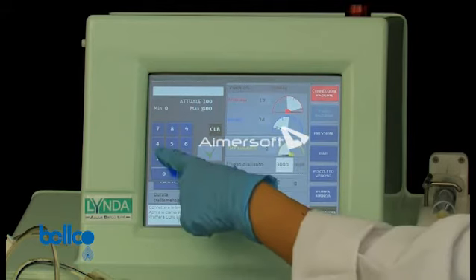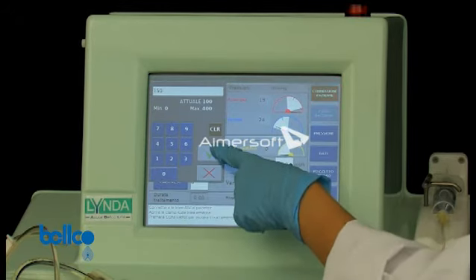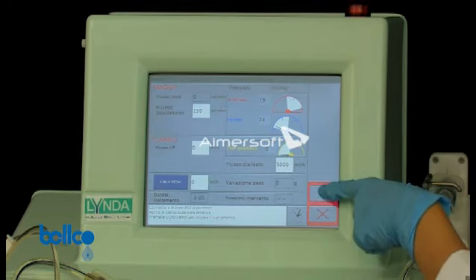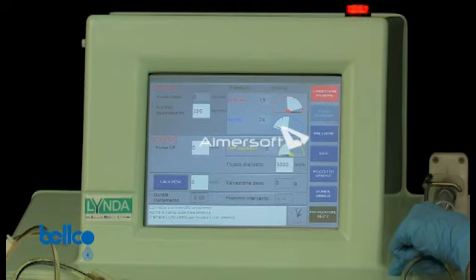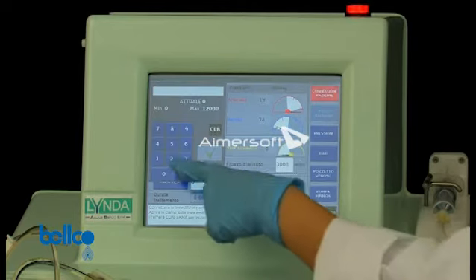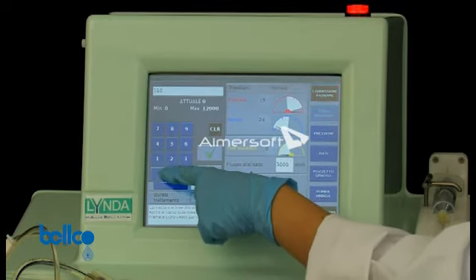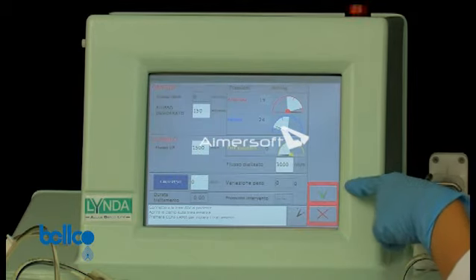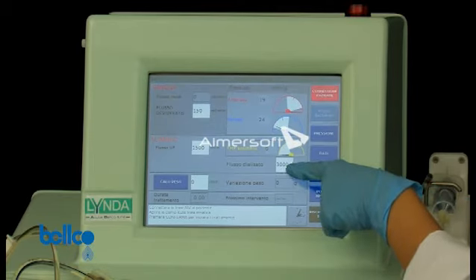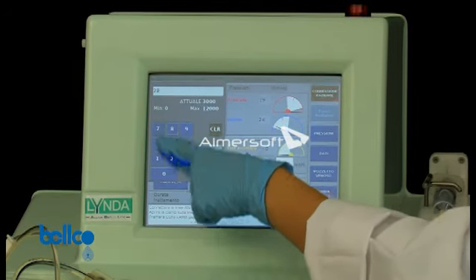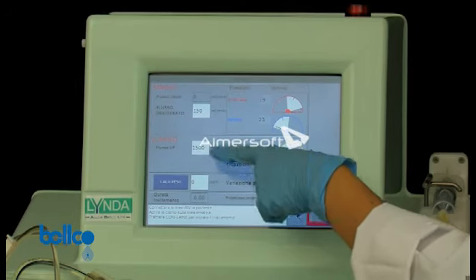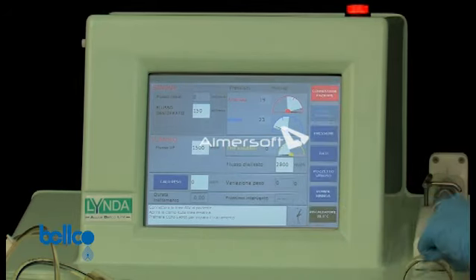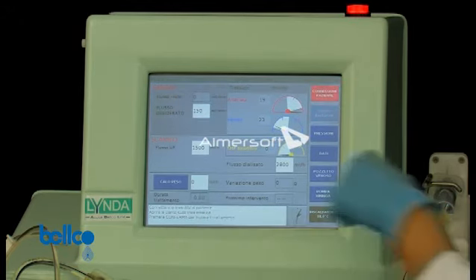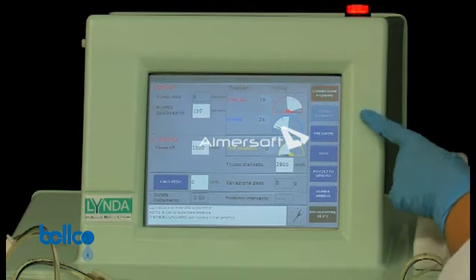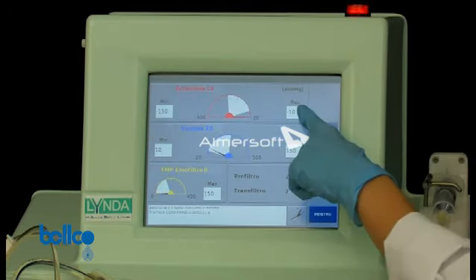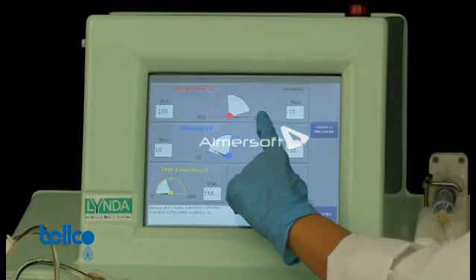Set the various treatment parameters: blood flow, UF flow, dialysate, and if necessary, weight loss. Tapping the pressures button, you can change the venous and arterial pressure range as well as the maximum TMP of the blood filter.